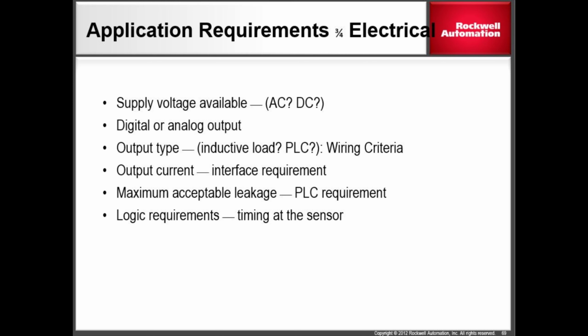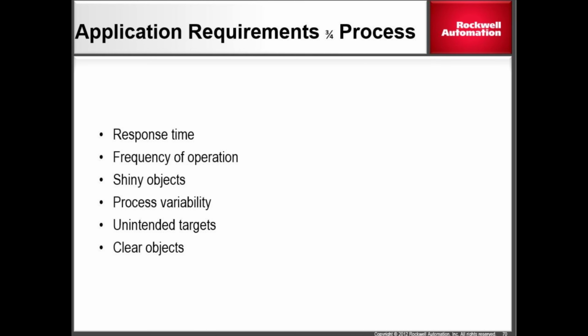Another thing about current, leakage current out of the device. Is that enough to not allow my PLC to shut off when it's supposed to? Sometimes the PLC can see leakage current as an input depending on the manufacturer of the PLC. Logic requirements, do I need timing in the sensor of some kind? Application requirements, response time. Does it have to be high speed? Am I looking at a bunch of targets running down a conveyor really fast where I've got to be able to switch back and forth from off to on, back to off, and back on again really, really quickly? That would be a response time issue.